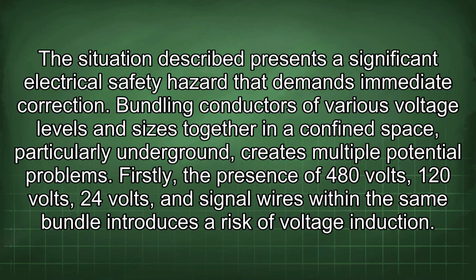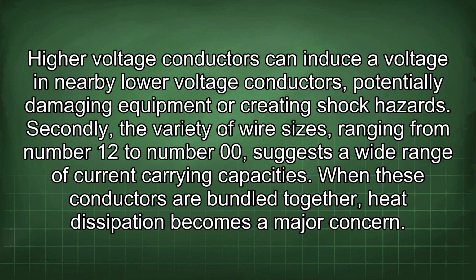The situation described presents a significant electrical safety hazard that demands immediate correction. Bundling conductors of various voltage levels and sizes together in a confined space, particularly underground, creates multiple potential problems. Firstly, the presence of 480 volts, 120 volts, 24 volts, and signal wires within the same bundle introduces a risk of voltage induction. Higher voltage conductors can induce a voltage in nearby low voltage conductors, potentially damaging equipment or creating shock hazards.